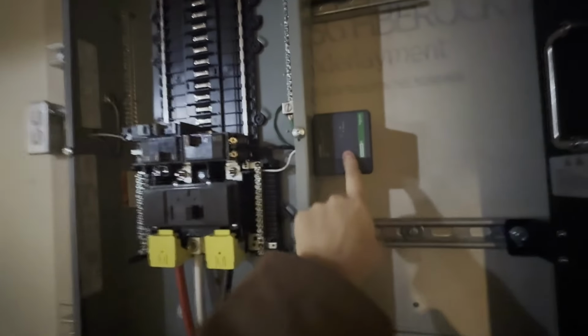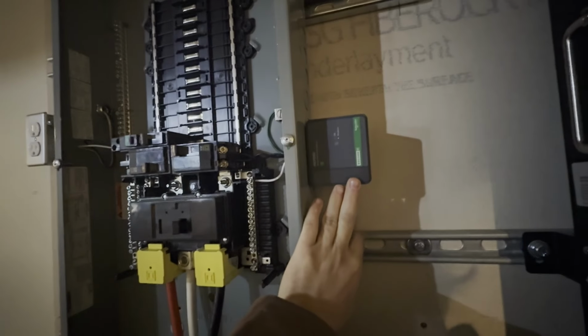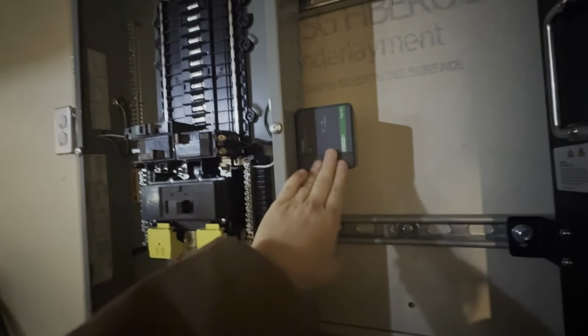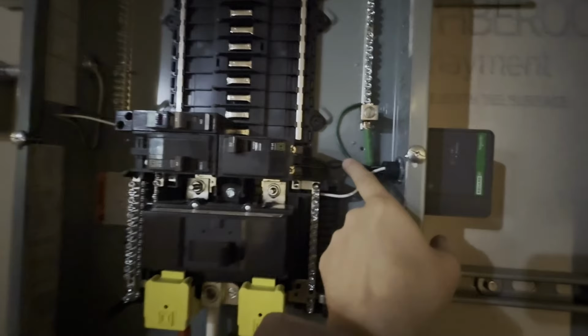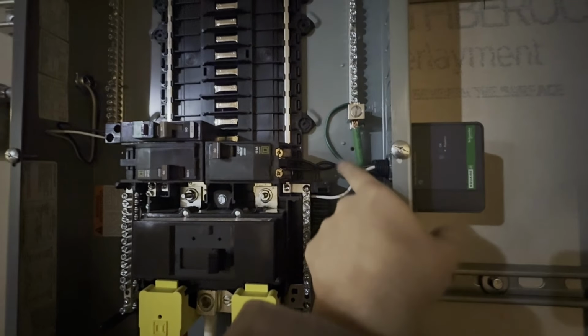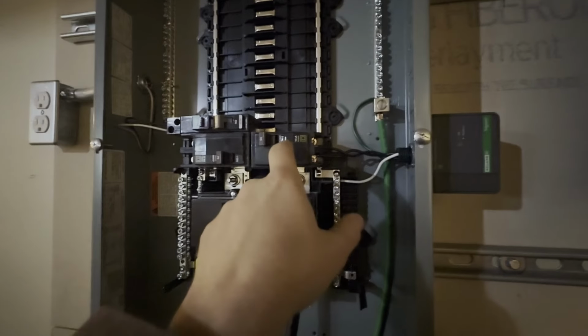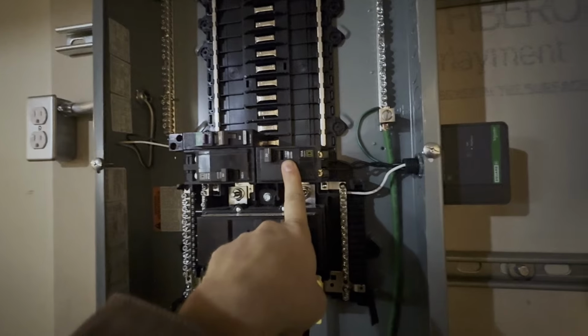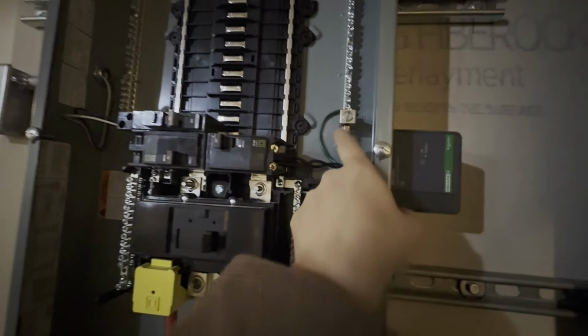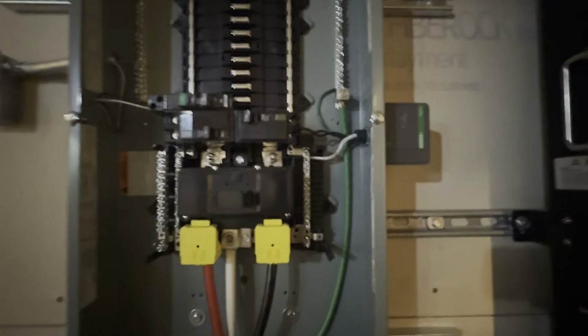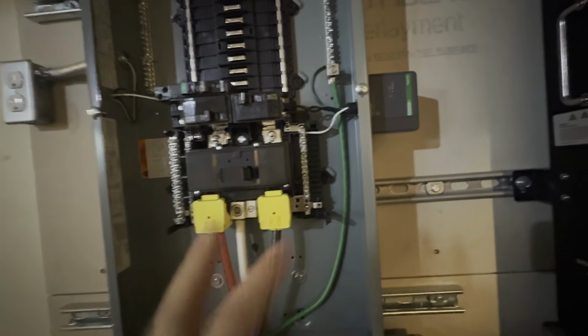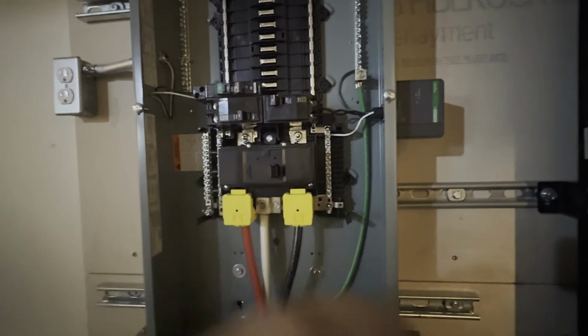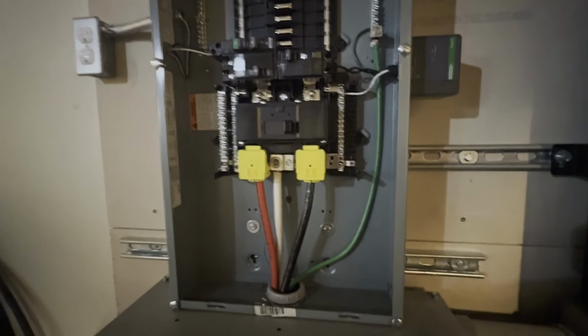The surge suppressor, so these things are neat. Basically, if there's a spike in voltage, this is going to, as quickly as it can, try and shunt that energy to ground. So in this case, yes, it's a 30 amp circuit and these are pretty small wires, but it's not actually carrying a lot of current. Its job is just to be connected to the two lines that are coming in and shunt stuff to ground as needed, right? So it's got the lives, the neutral, and then the ground. The shorter those wires are, the faster it can work, basically. The way I've always thought about it is like the pulse, like if there's a surge, right?